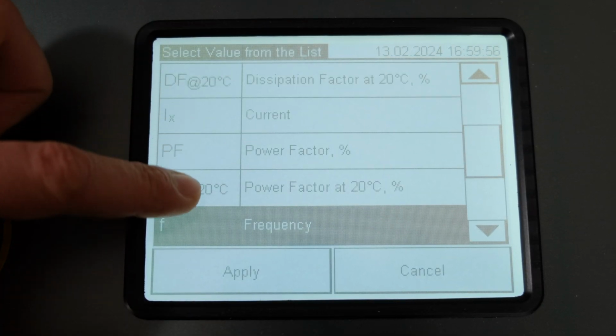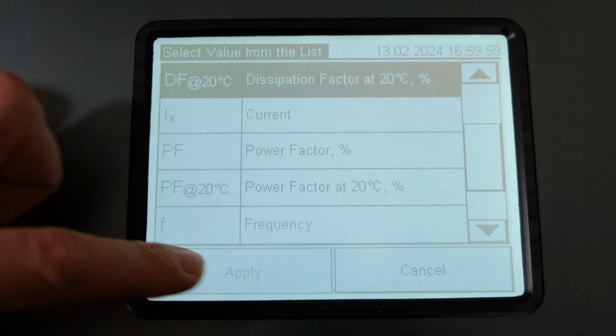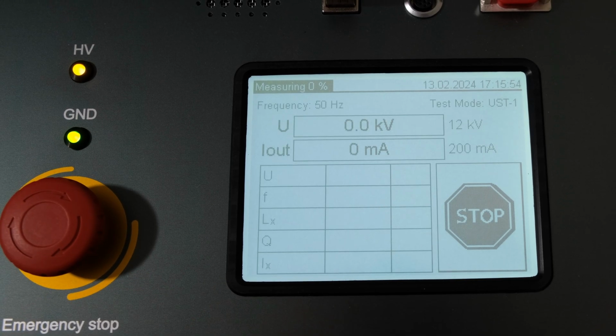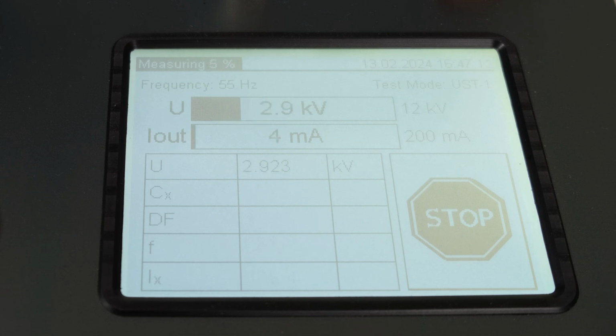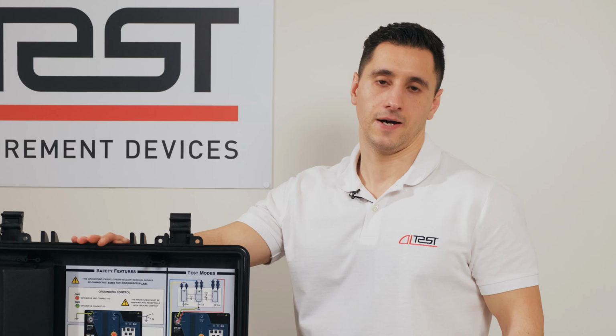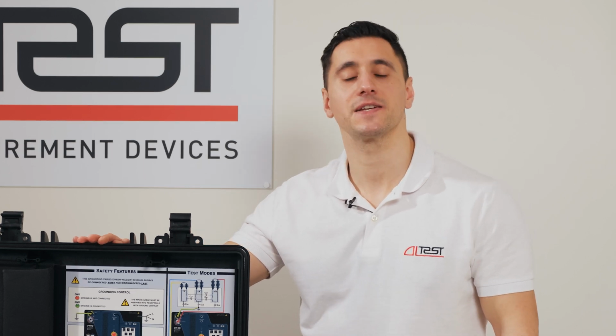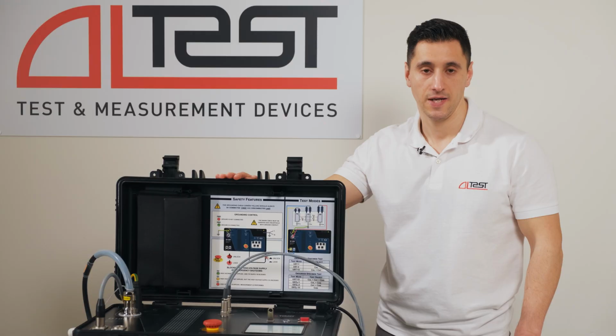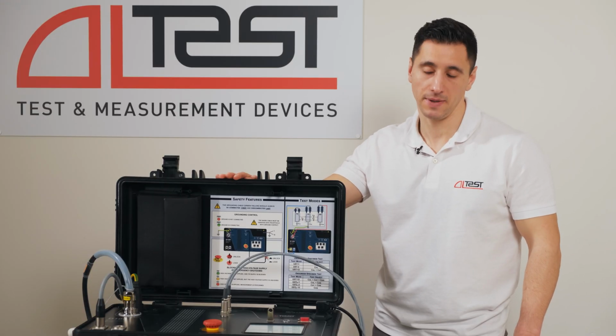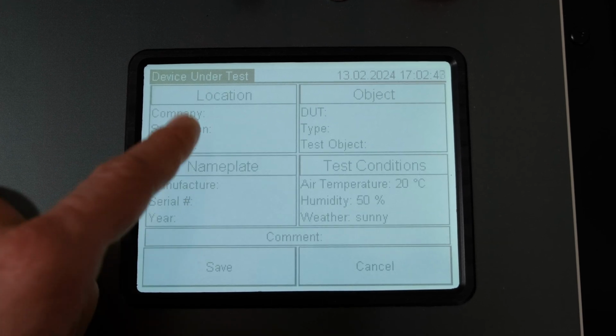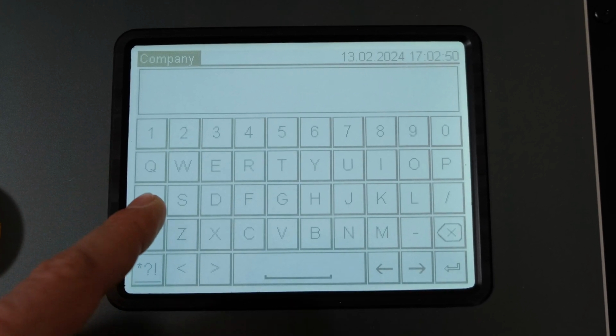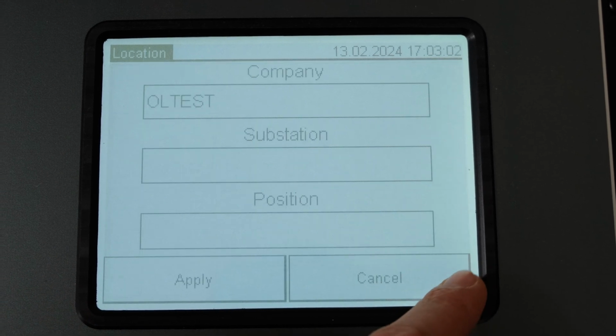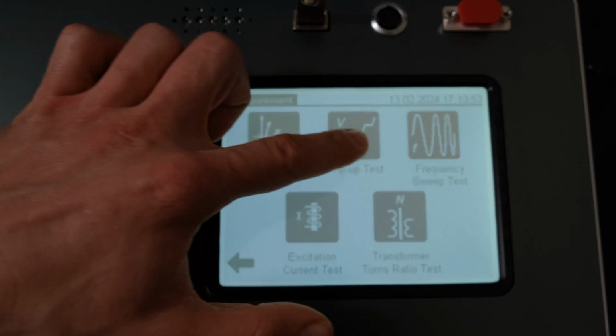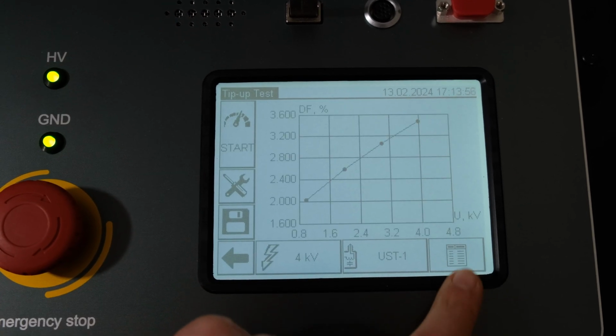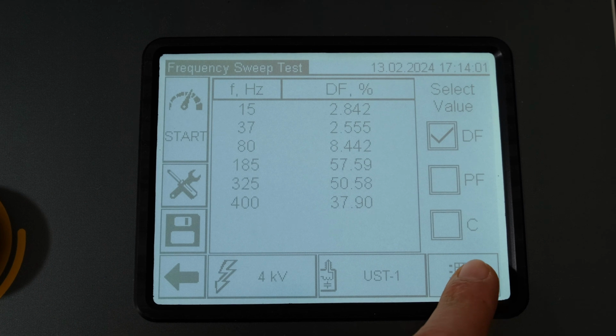You can measure many parameters with this device. The sequence of the measurement results can be changed. All settings are done. Let's start testing. During the test process, the device automatically performs measurements at 2 frequencies. The adaptive filtering algorithm reduces the test time at low interference currents and provides a high level of suppression at high interference currents. The measurement results can be archived. In this case, you can fill in the object profile by entering the appropriate identifiers. It is possible to determine the dependence of insulation parameters on voltage and the dependence of insulation parameters on frequency.